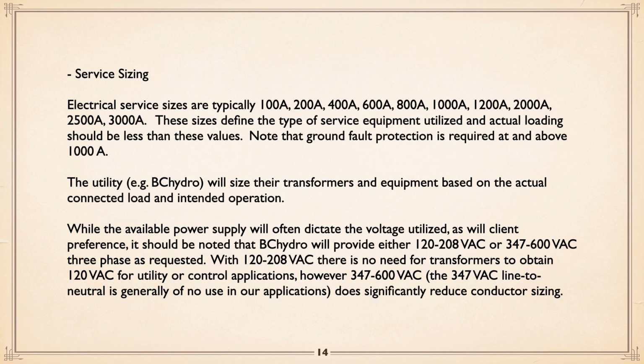Now, what happens is your service equipment and everything else will be rated, let's say, 200 amp. And of course, your demand should be less than 200 amp with the pumps and everything else. Utilities will ask what your load actually is, and they will size their own transformers as they see fit, fine and dandy. To you, though, it's a 200 amp service or whatever.